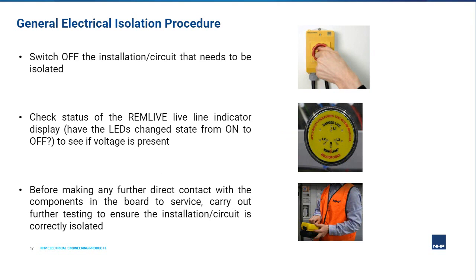Once the correct isolation points or devices of the system have been identified, isolate by switching them off. Keeping an eye on the REMLIVE liveline indicator, check if the LEDs have changed state from on to off. If the LEDs have turned off, it indicates that there is an absence of voltage. However, don't yet make any contact with components inside the panel. It's required for the service technician to carry out further testing using a multimeter.